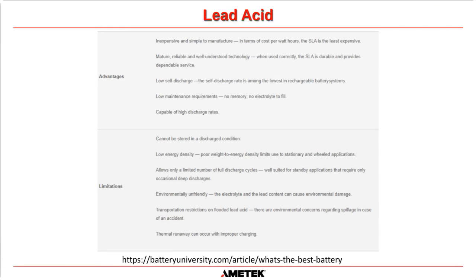Lead acid, the advantages: mature, reliable, and well understood technology. It's what's used in the plants all over the world. When used correctly, lead acid is durable and provides dependable service. It's got a low self-discharge. You can leave it on a shelf and you only have to recharge it after 6 months if it's stored at 77 degrees. Has very low maintenance requirements. It has no memory issues, and for a valve-regulated lead-acid battery, it has no electrolyte to fill. And they're capable of very high discharge rates.